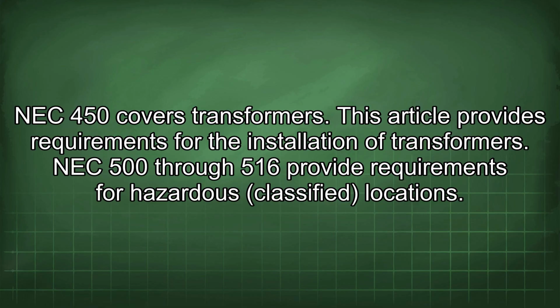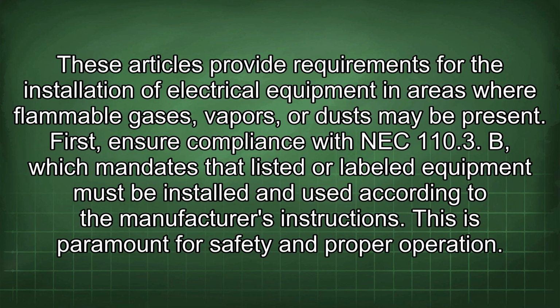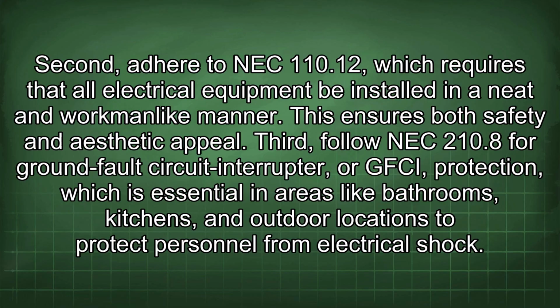NEC 500 through 516 provide requirements for hazardous classified locations. These articles provide requirements for the installation of electrical equipment in areas where flammable gases, vapors, or dust may be present. First, ensure compliance with NEC 110.3(B), which mandates that listed or labeled equipment must be installed and used according to the manufacturer's instructions. This is paramount for safety and proper operation. Second, adhere to NEC 110.12, which requires that all electrical equipment be installed in a neat and workmanlike manner. This ensures both safety and aesthetic appeal.